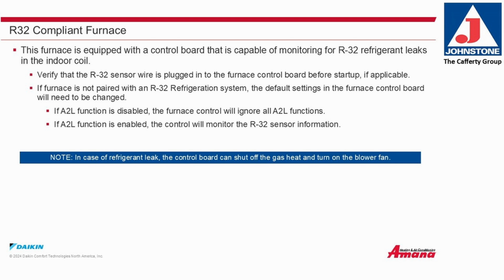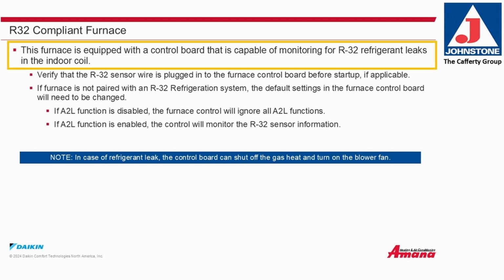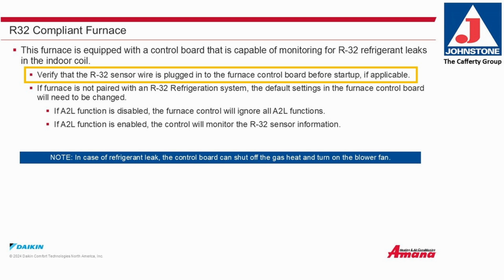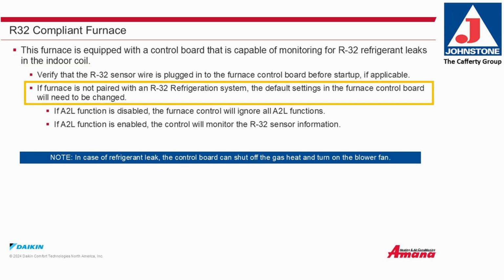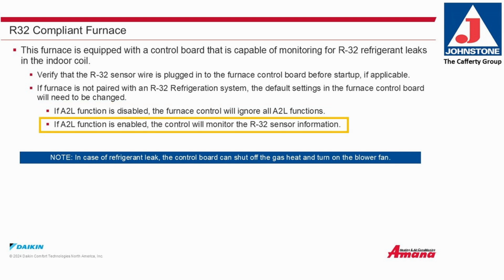R32 compliant furnace. This furnace is equipped with a control board that is capable of monitoring for R32 refrigerant leaks in the indoor coil. Verify that the R32 sensor is plugged in to the furnace control board before startup, if applicable. If the furnace is not paired with an R32 refrigeration system, the default setting in the furnace control board will need to be changed. If the A2L function is disabled, the furnace control will ignore all A2L sensors. If A2L function is enabled, the furnace will monitor the A2L sensor information.